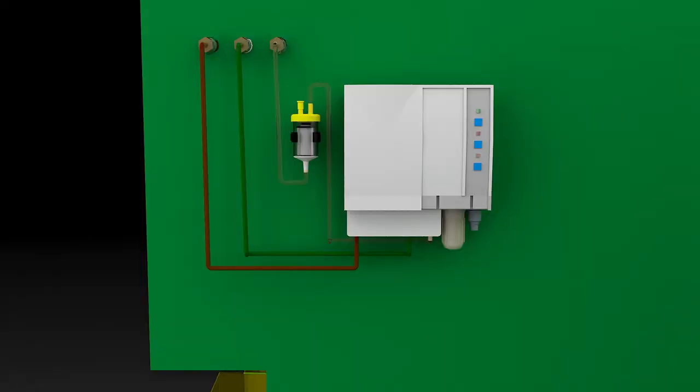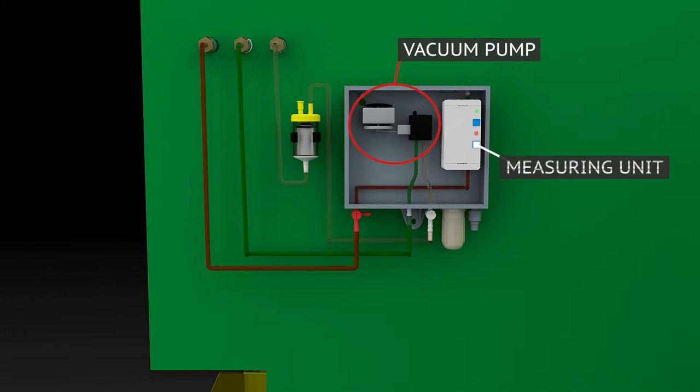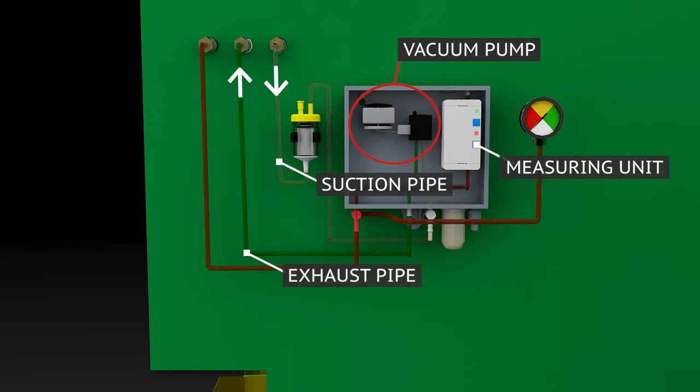In the leak detector are located a vacuum pump and a measuring unit for vacuum control, shown here with a manometer. Air from the monitoring room is withdrawn through the suction pipe and directed via the exhaust pipe into the tank.